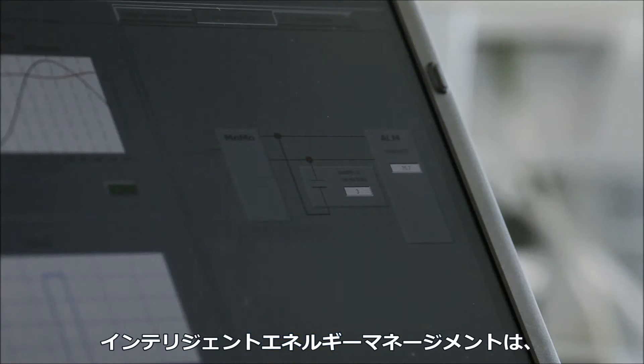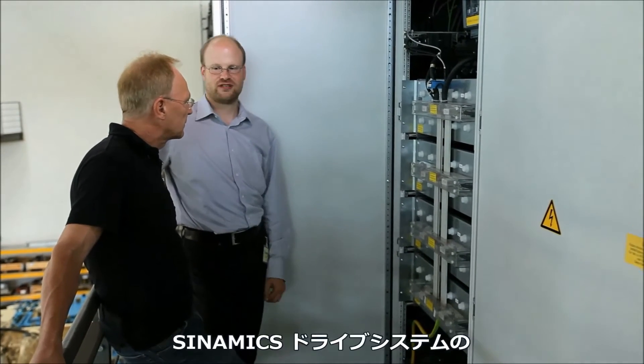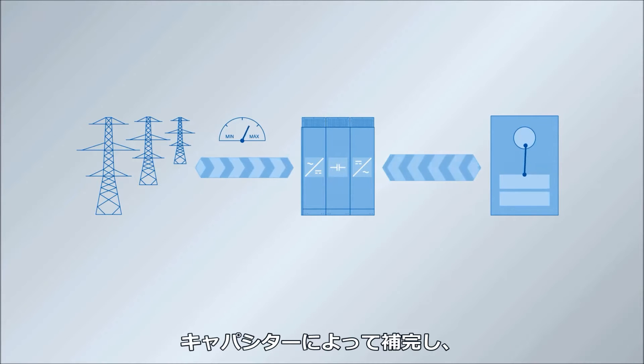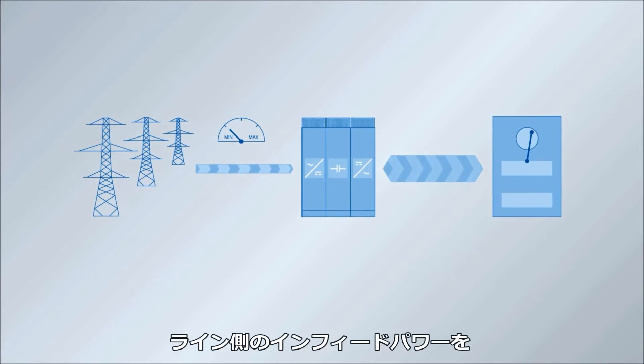Using intelligent energy management, high current peaks resulting from the press process are handled by kinetic or capacitive storage devices connected to the DC link of the SINAMICS drive system. As a consequence, the line-side in-feed power is reduced to a minimum.